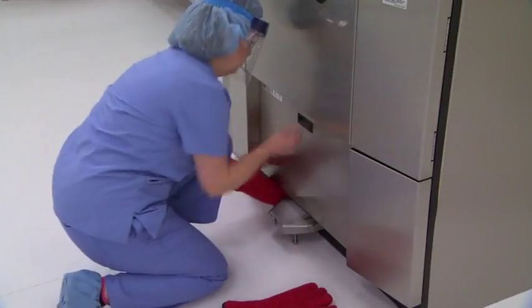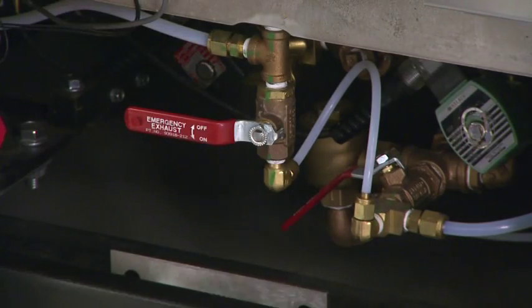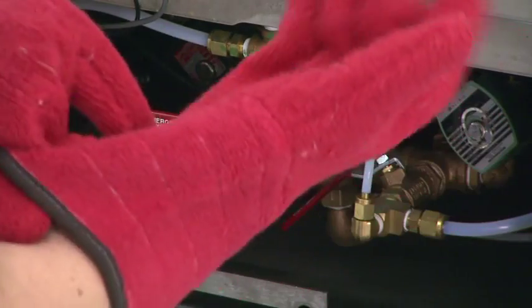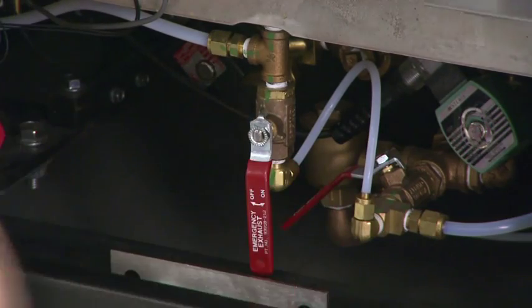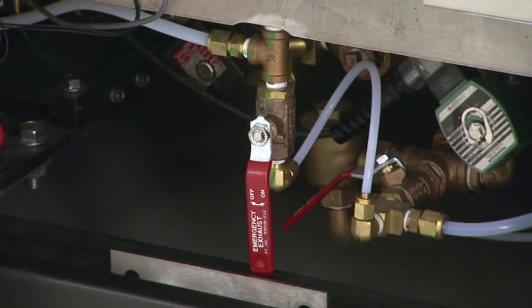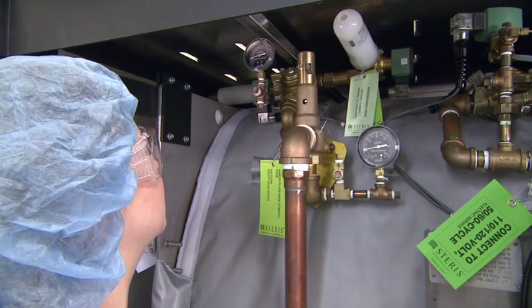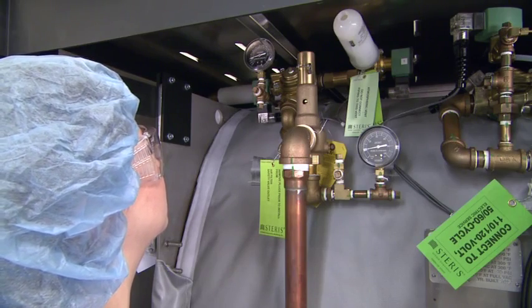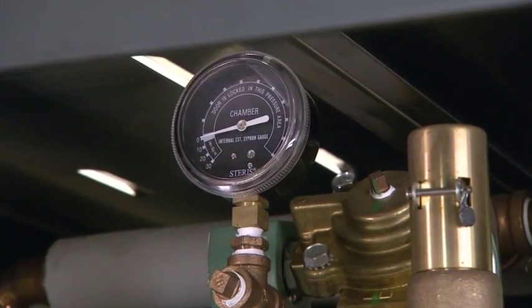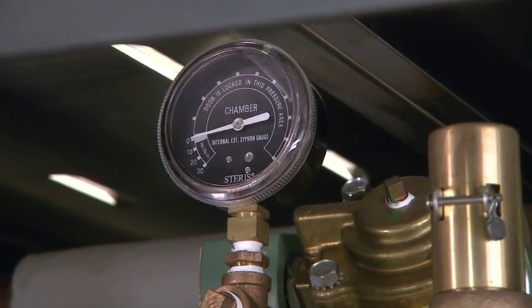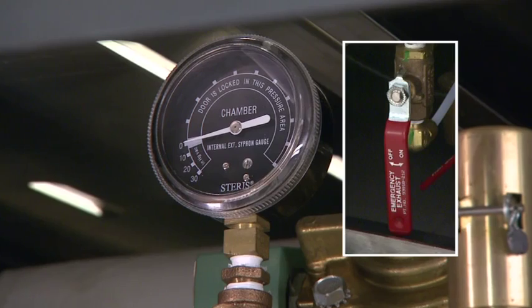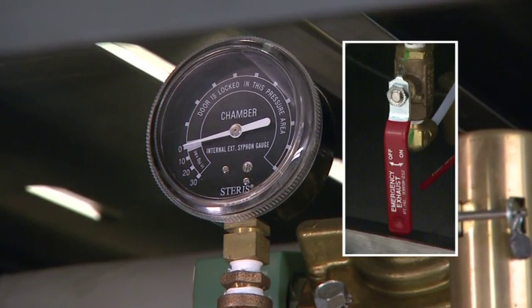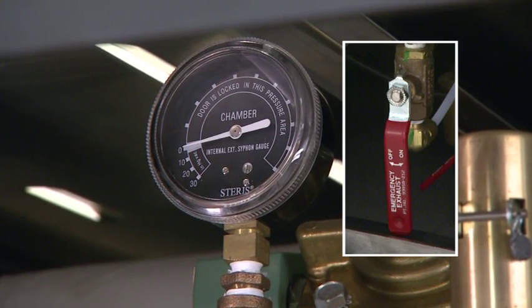To open the door in an emergency, remove the lower front panel on the sterilizer. Open the chamber emergency exhaust valve located at the bottom of the unit behind the lower front panel. Do not open the second valve at this time. Monitor the chamber pressure gauge located on the front left side panel. Wait until the gauge reads 0 pounds per square inch pressure in the sterilization chamber. The valve must remain open even after the chamber pressure reaches 0.